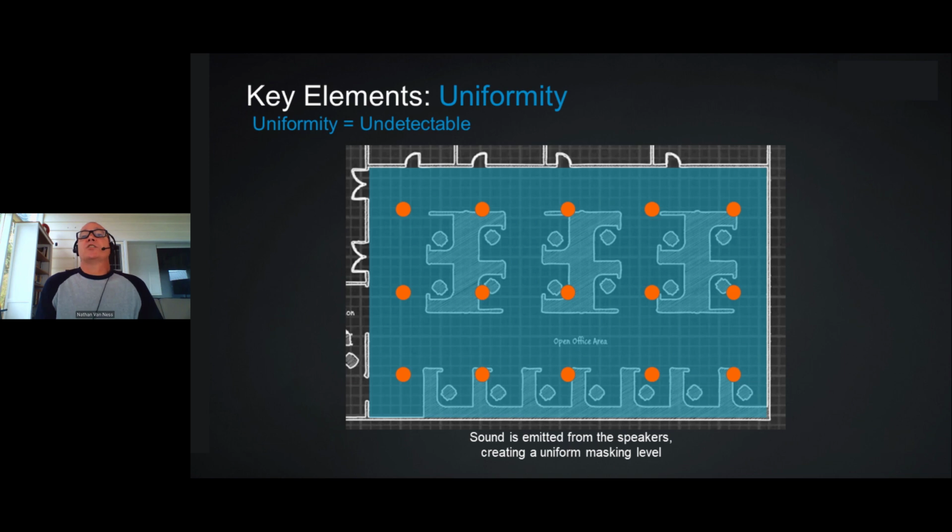And a large part of the philosophy of sound masking is the idea that it should be as uniform as possible. The more uniform a noise is, the easier it is for us to tune it out. In every respect, sound masking should be unwavering, constant, and unchanging. Any hot spots, dead spots, or other changes to the noise only serve to increase the likelihood of the occupants noticing it. So for this reason, we often install sound masking in spaces where we are not necessarily concerned with speech privacy, like hallways or corridors, reception areas, lobbies, transitional areas, etc.